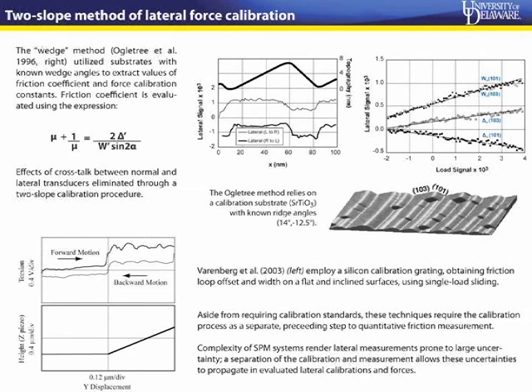This is essentially what I showed in the previous slide. You'll notice that the W's overlap because your friction shouldn't change even if you change angles. Now, the two equations that we saw in the previous slide, if you eliminate Cx and Cy, you end up with this quadratic equation, which is one of the formulations of the wedge method by Ogletree and others. Since then, other methods have sought to extend it. Varenberg in 2003 proposed a similar method, which was applicable to colloidal probes also. And this is just two examples of a wide variety of methods which have been used for AFM tip calibration for lateral force measurements.